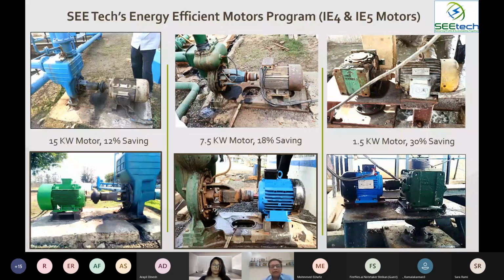Same way, in the 7.5 kilowatt motor, we wanted speed variation as well. Here the feasibility for IE5 motor was better, because IE4 motor will also give you saving, IE5 will also give you saving. But your fine levels of calculations will give you feedback on which one is more feasible, both technically and financially, so you make a fine choice. The 7.5 kilowatt motor resulted in 18% savings.